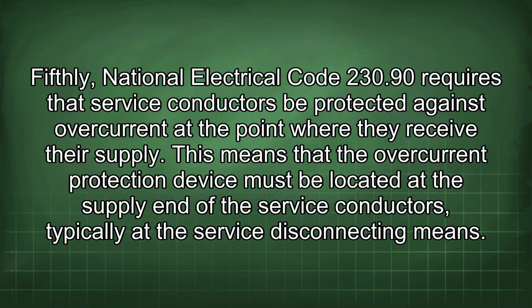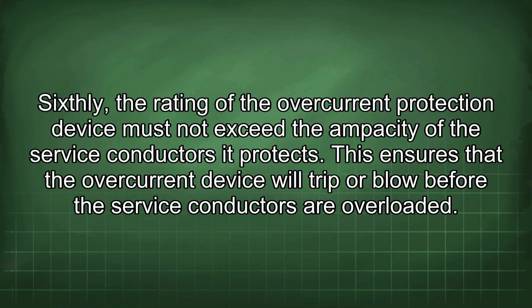Fifthly, National Electrical Code 230.90 requires that service conductors be protected against overcurrent at the point where they receive their supply. This means that the overcurrent protection device must be located at the supply end of the service conductors, typically at the service disconnecting means. Sixthly, the rating of the overcurrent protection device must not exceed the ampacity of the service conductors it protects. This ensures that the overcurrent device will trip or blow before the service conductors are overloaded.